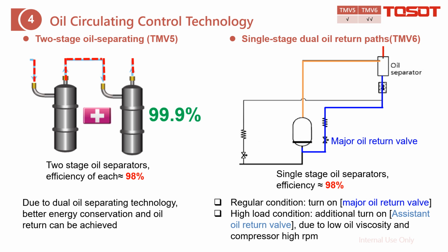It is quite enough for the regular condition. Here, what I mean by the regular condition is when the outer ambient is not low. If the outer ambient becomes very low, for example, as low as minus 22 degrees Fahrenheit, which is minus 30 degrees Celsius, at that time the oil viscosity is high, which also means the oil is not that easy to flow back to the compressor. With only the major oil return path, the amount would not be enough.